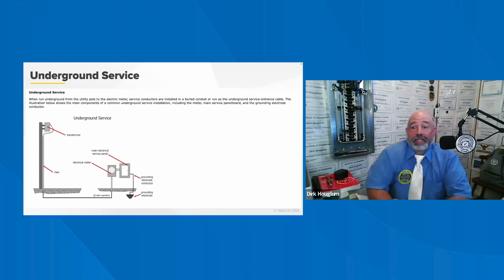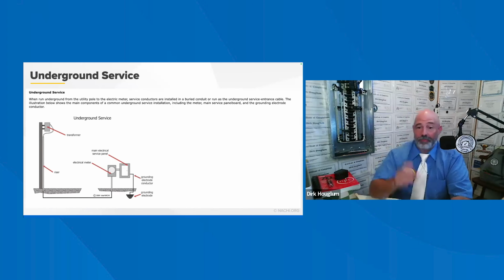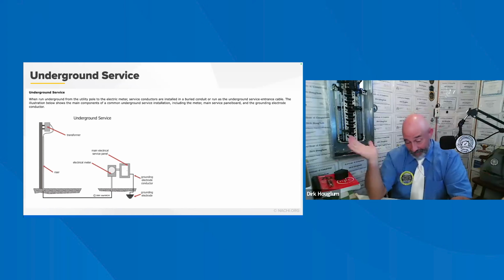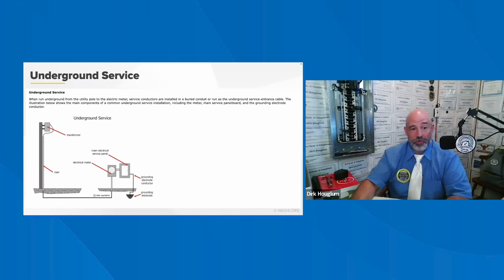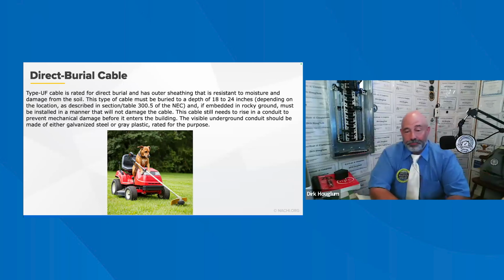The service lateral typically terminates at the meter or the main disconnect enclosure. The service underground conductors, the service lateral, is an underground system for the service entrance conductors. For underground service, the service entrance conductors connect to the service lateral and run to the terminals of the service equipment, likely the main service disconnect. Hopefully that was not too confusing. So it's either running underground or overhead. It's still a lateral. So the direct buried cable.